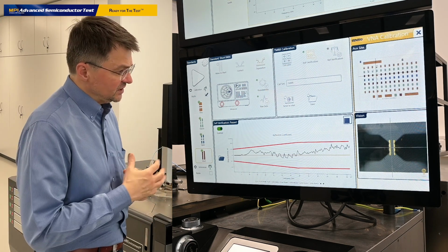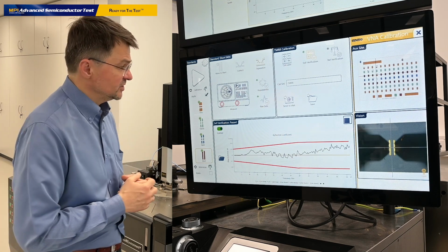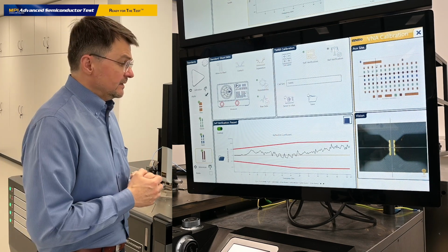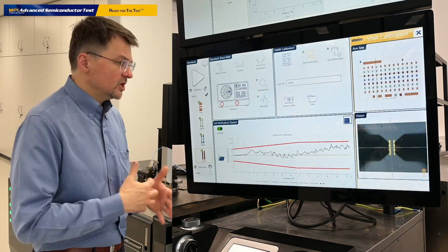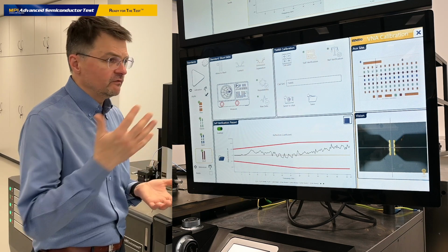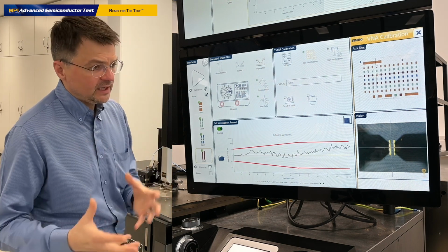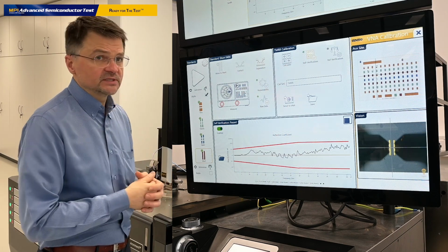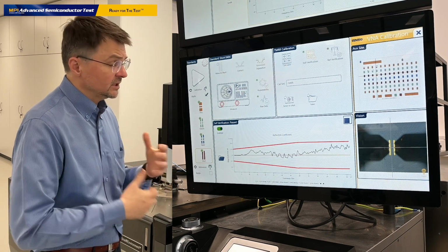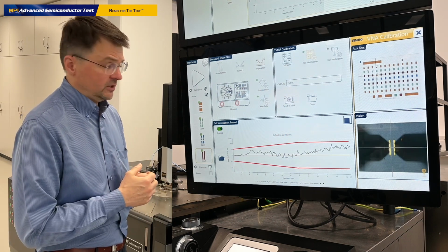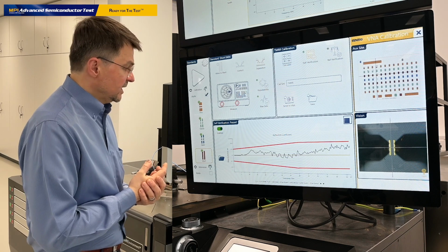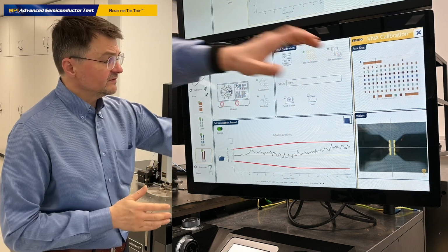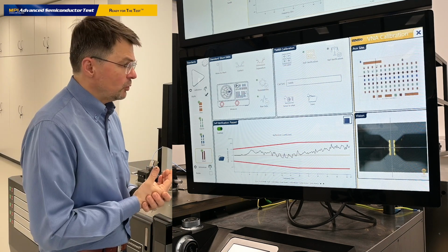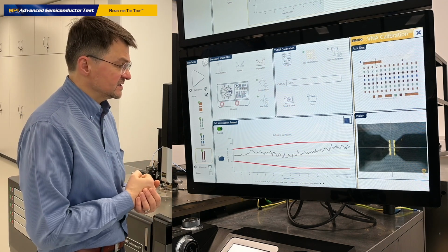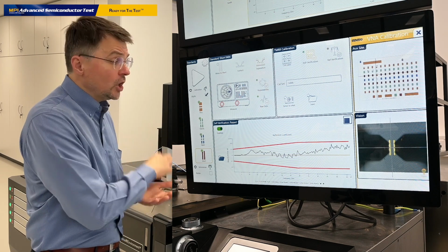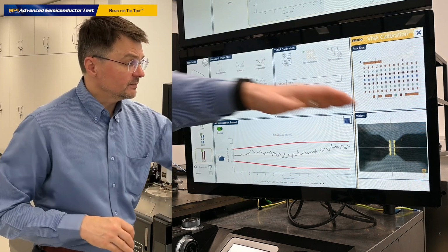What type of approaches do engineers use to make sure that the SOLT calibration algorithm was completed successfully? This is the measurement of the golden devices, or measurement of verification elements which were not involved in the calibration process, where we compare the corrected results versus expected results of one or another calibration standard and can conclude that our calibration was executed accurately. Calibration quality is acceptable. Calibria realizes this method. We call it reference verification. It means verification of the calibration quality based on the measurements of the reference devices. Such reference devices can be located on wafer, or they also can be located on the calibration substrate.